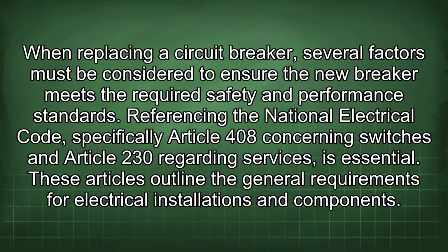When replacing a circuit breaker, several factors must be considered to ensure the new breaker meets the required safety and performance standards. Referencing the National Electrical Code, specifically Article 408 concerning switches and Article 230 regarding services, is essential. These articles outline the general requirements for electrical installations and components.